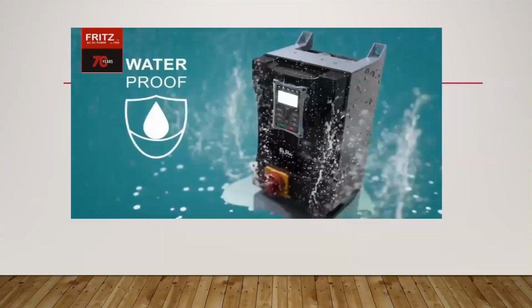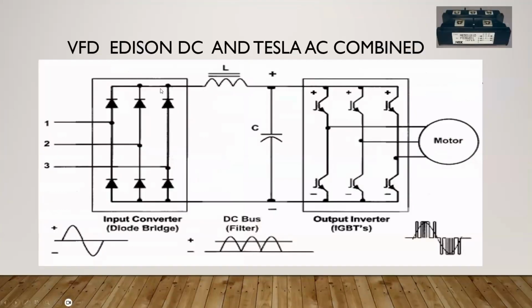Also, the controllers today are able to take direct DC off of the power source, off of a solar system. So if you've got batteries on a regulated circuit, there are two terminals in there, and we can bring DC directly in. We put an extra protection diode in between, but a lot of that's being done today. And then there's software that can regulate the reading of that solar, and it can be pulling off of the solar or off of the power source, either single or three-phase. So it's made a lot of flexibility.